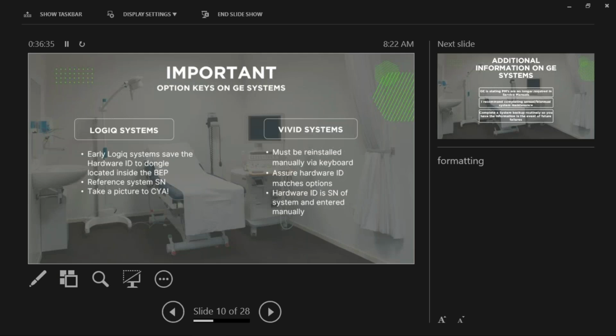What does that mean? If they don't match, then you go grab the USB from the other computer that you pulled out, and you just swap it over, right? Typically when people sell the PC or the computer, they pull theirs out, so a lot of people forget to move it over. And if you've moved it over and it still doesn't match, then you're going to have to get a GE field service engineer to come in and change it, or make sure that the hardware ID is correct.